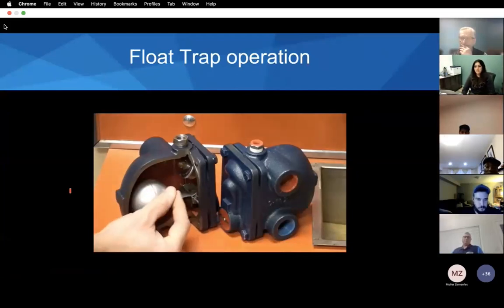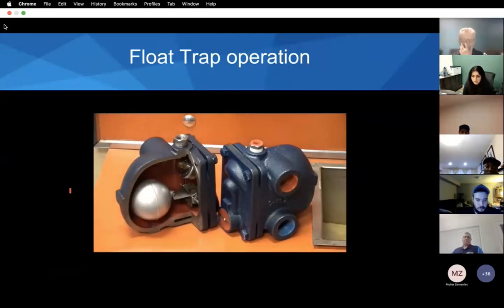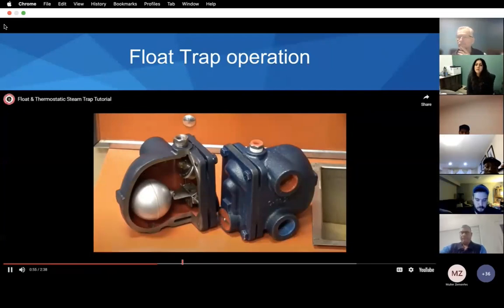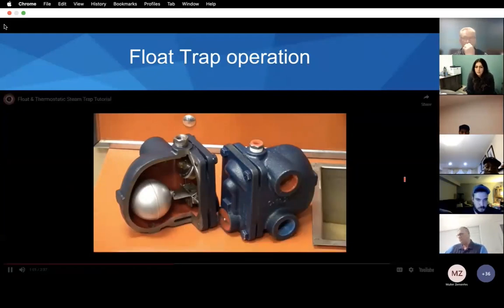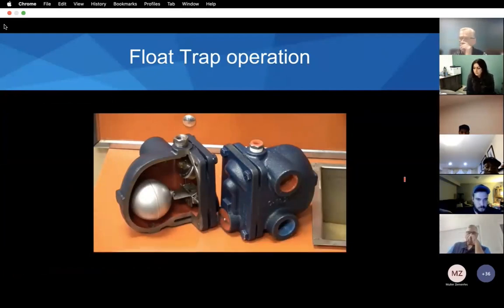When this space is filled with hot steam, the thermostatic valve is closed. Non-condensables, such as air, mix with the steam and cool the space near the top of the trap. When the bellows element cools sufficiently, the thermostatic valve will open and vent these gases into a passage leading to the trap discharge.